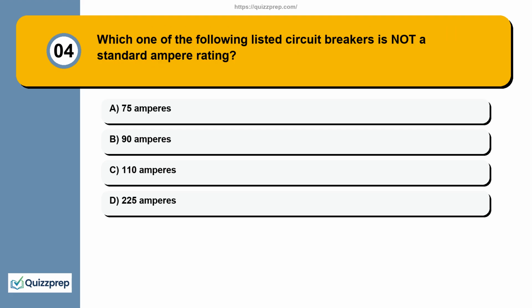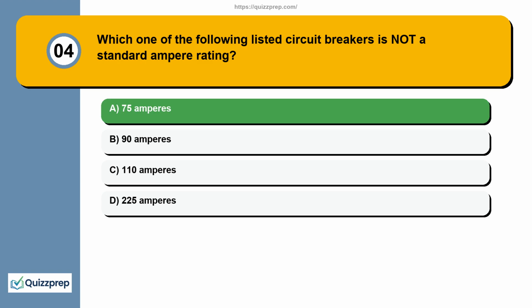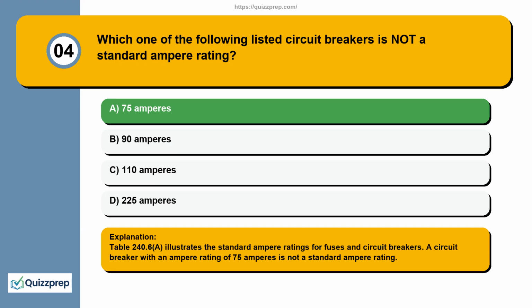Question 4. Which one of the following listed circuit breakers is not a standard ampere rating? 75 amperes, 90 amperes, 110 amperes, 225 amperes. Table 240.6(A) illustrates the standard ampere ratings for fuses and circuit breakers. A circuit breaker with an ampere rating of 75 amperes is not a standard ampere rating.